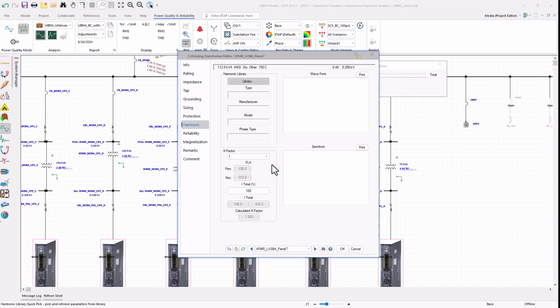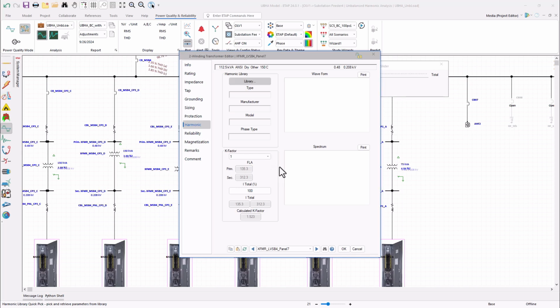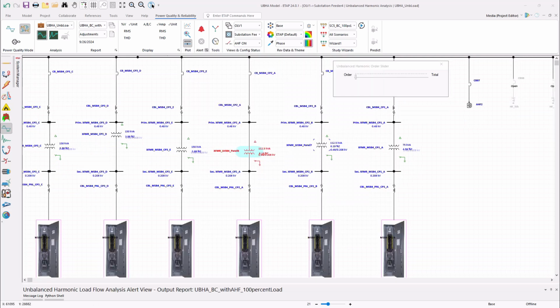And in such cases, if clients were to choose higher K-rated transformers, there is a feature to choose the K rating of the transformer here and perform evaluation with a different scenario in such case. So as part of this analysis, in addition to calculating the K factor due to the harmonic composition and the load current, ETAP also identifies the derating requirements of the transformers and flags them in the alert view.